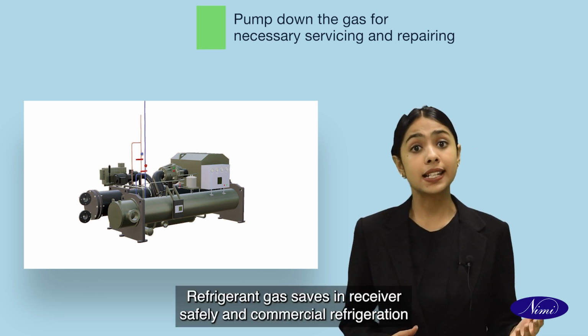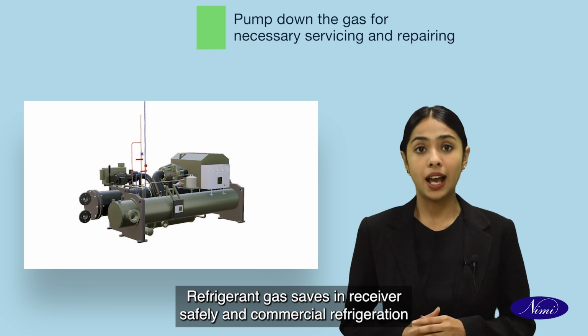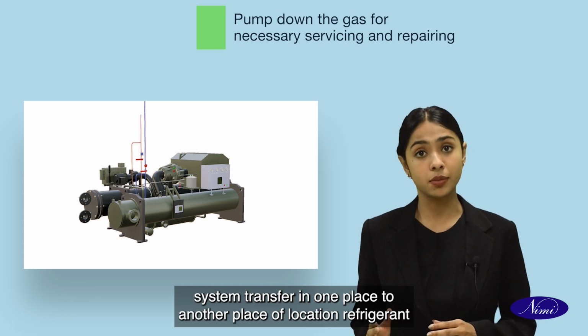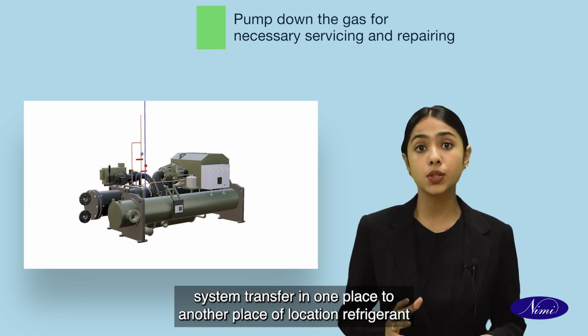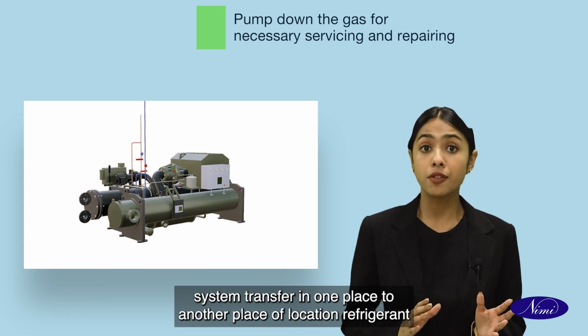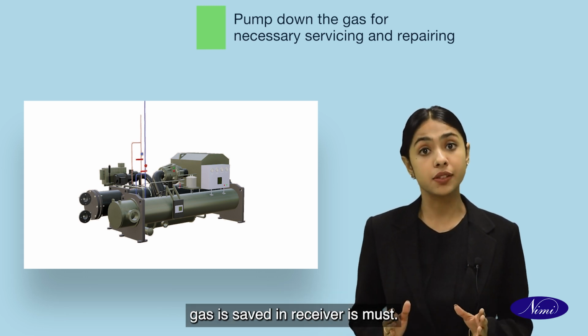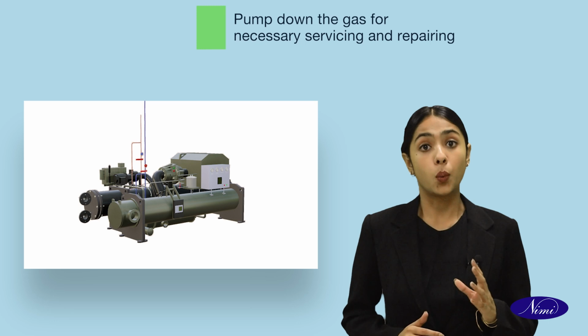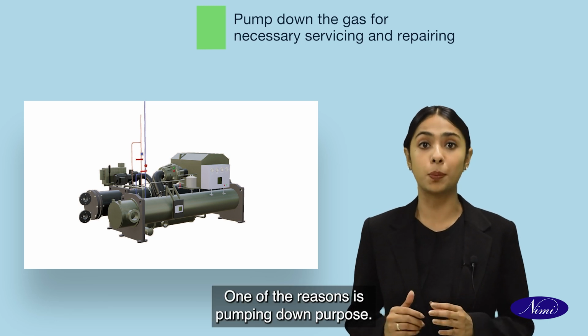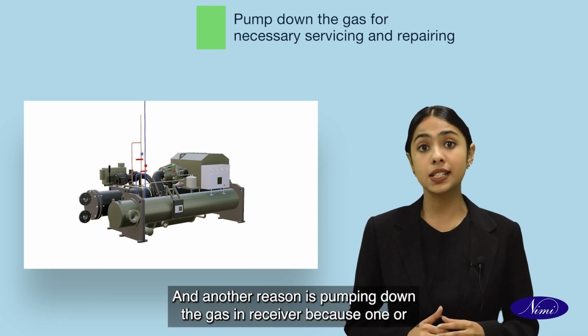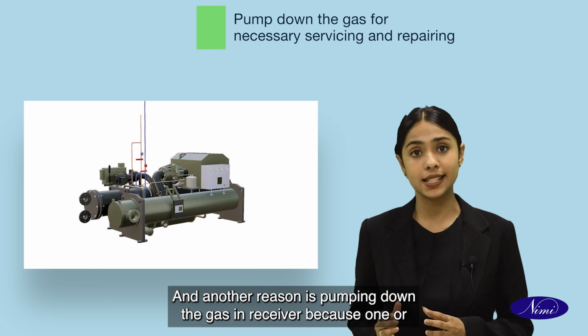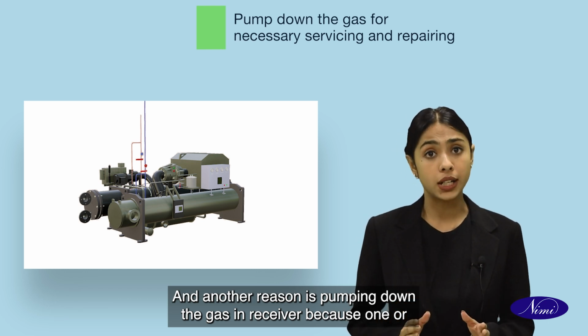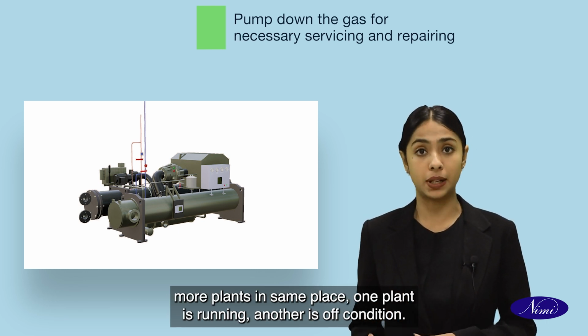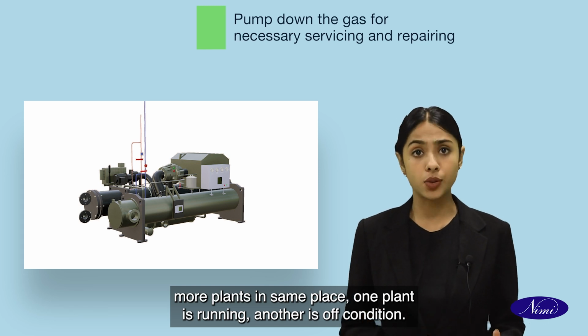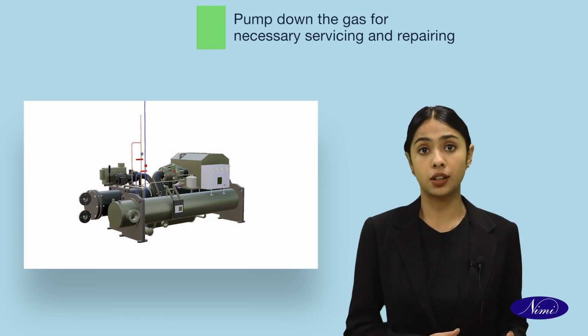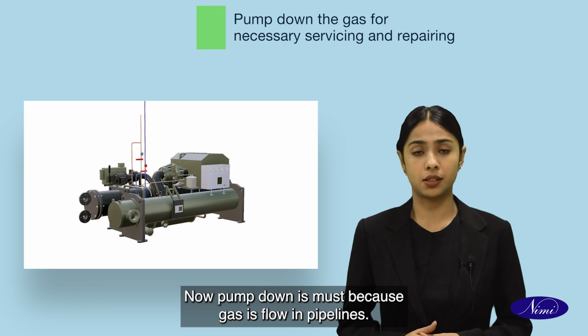Refrigerant gas is saved in the receiver safely, and in commercial refrigeration systems it is transferred from one place to another location. Saving refrigerant gas in the receiver is a must. One of the reasons is the pumping down purpose. Another reason is that there may be one or more plants in the same place, where one plant is running and another is off. Now pump down is a must.